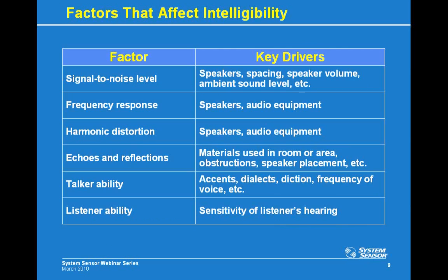When talking about intelligibility, I have often heard people say that either the speakers that they are installing are the most intelligible or the speakers that we make are the most intelligible. And I always like to point out that neither of these statements should be used when talking about intelligibility, because intelligibility is not something that can be specified on a data sheet. There are a lot of different variables that will play into the intelligibility of a message that is being played, so it is not something that is purely up to the speaker itself.